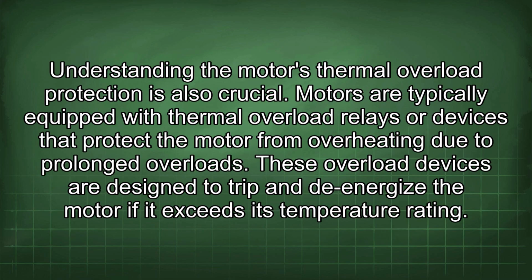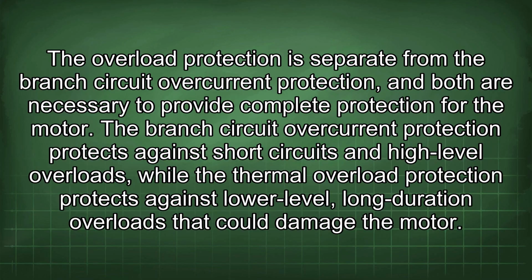Understanding the motor's thermal overload protection is also crucial. Motors are typically equipped with thermal overload relays or devices that protect the motor from overheating due to prolonged overloads. These overload devices are designed to trip and de-energize the motor if it exceeds its temperature rating. The overload protection is separate from the branch circuit overcurrent protection, and both are necessary to provide complete protection for the motor. The branch circuit overcurrent protection protects against short circuits and high-level overloads, while the thermal overload protection protects against lower-level, long-duration overloads that could damage the motor.